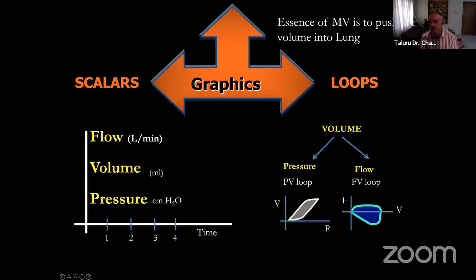Whenever we see a scalar, how to identify it is, it always starts from one point and always goes in the right direction. It starts from the point, it never comes back there. It goes from one point towards the right. So that is one way of looking at it. And whenever you see a major representation below the baseline, you can be sure that it is a flow kind of loop or scalar. If you go back and see here, whenever there is a representation below the baseline, flow has to be a component. So it will be a flow versus volume loop. And once you come here, it will be a flow versus time scalar. Whenever you see a major representation below the baseline, a flow component will be there. So there are three scalars, flow, pressure, and volume, and they start from one point and always move to the right. That's how it moves. All the pressure, volume, everything moves like that.